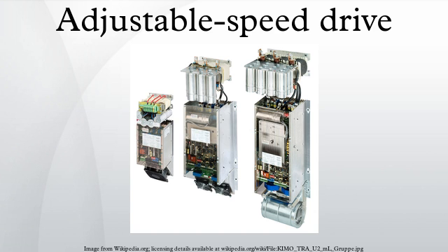Slip energy recovery systems return energy to the WRIM stator bus, converting slip energy and feeding it back to the stator supply. Such recovered energy would otherwise be wasted as heat in resistance-based WRIM drives. Slip energy recovery variable speed drives are used in such applications as large pumps and fans, wind turbines, shipboard propulsion systems, large hydro pumps, generators and utility energy storage flywheels.